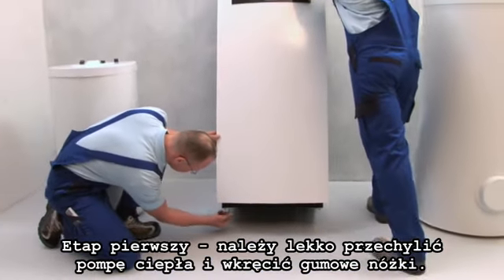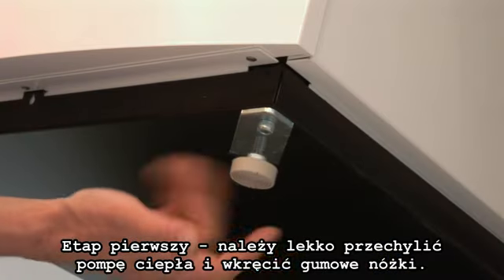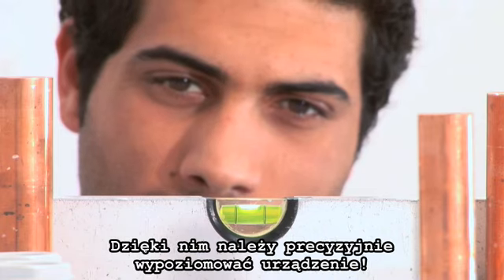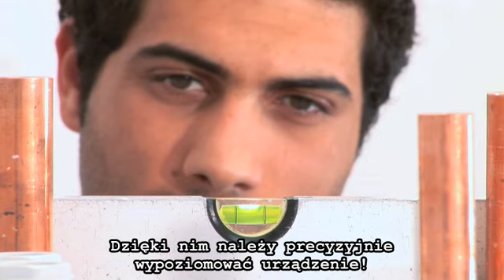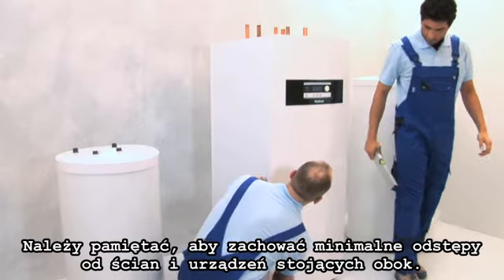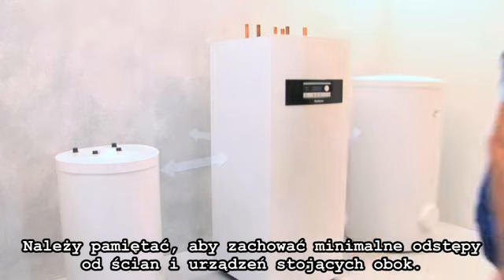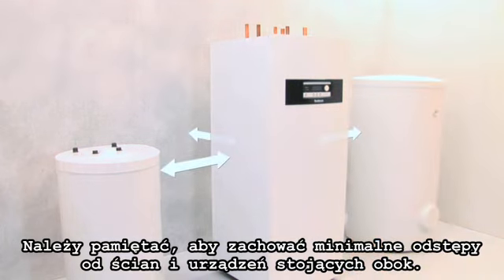First, tilt the heat pump slightly and screw on the rubber feet to the bottom side. They allow the device to be leveled. Please bear in mind that you have to maintain the specified minimum clearances to the surrounding devices and the walls.